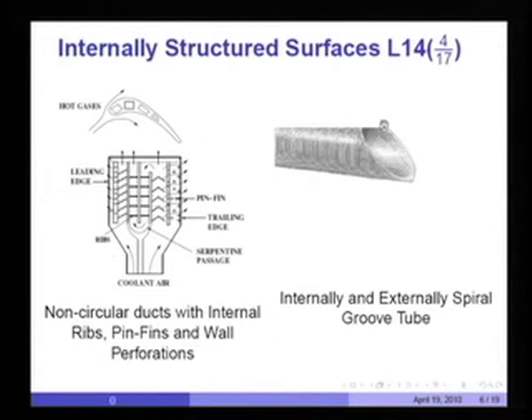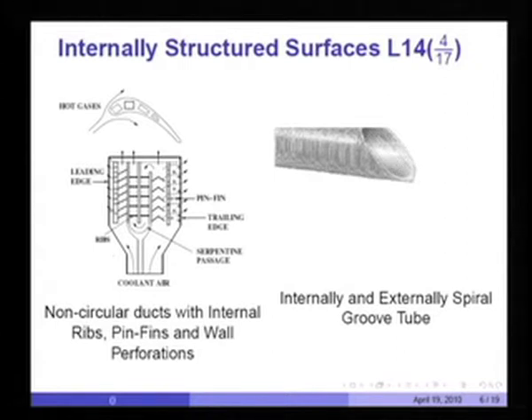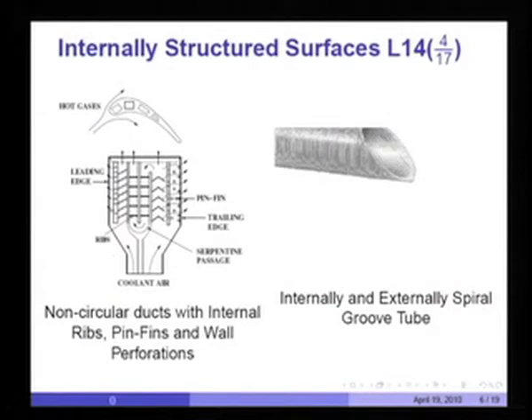A tube extensively used in the refrigeration and air conditioning industry has spiral grooves etched on both the inside and outside surfaces. These grooves are cut out of the copper tube and the near-surface structure is very tiny. The height of the grooves just exceeds the laminar sublayer in a turbulent flow. The purpose is to ensure that the sluggish laminar sublayer is continuously disrupted, thereby enabling enhanced heat transfer. The same is the purpose of internal rib roughnesses.